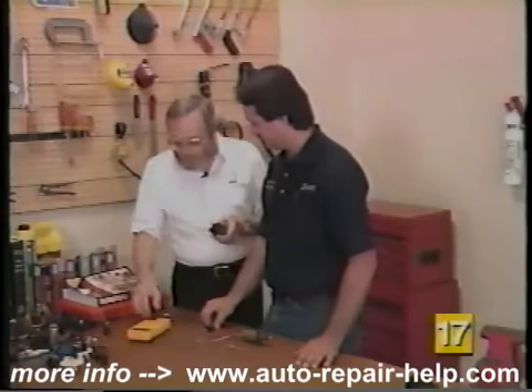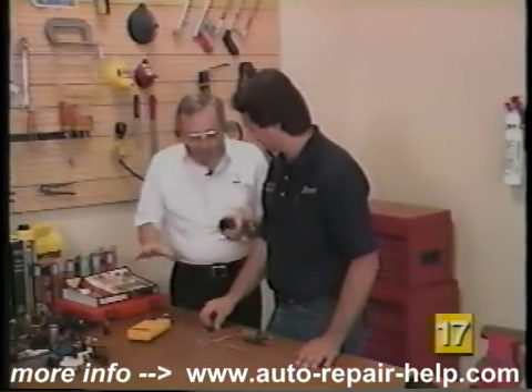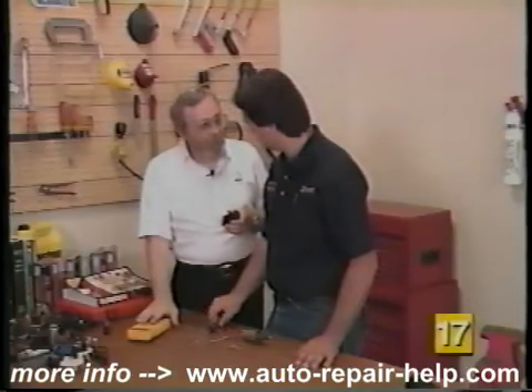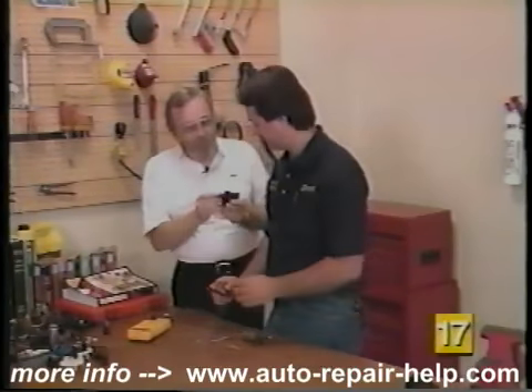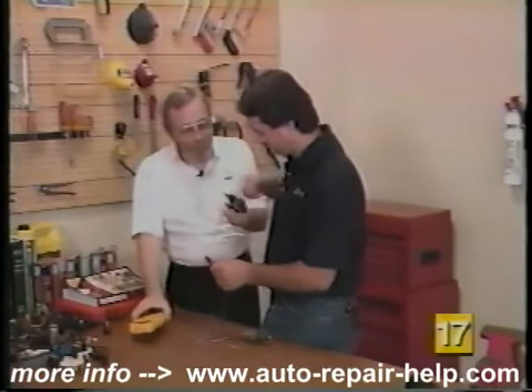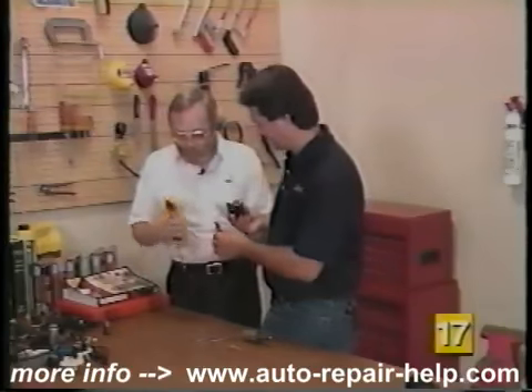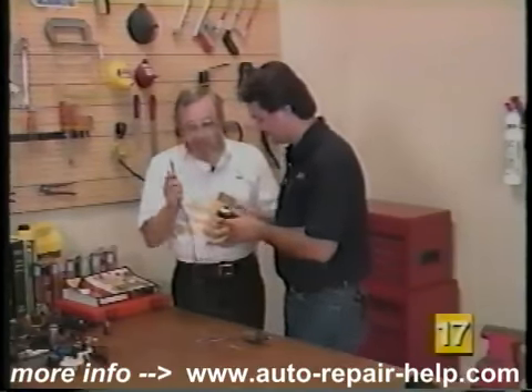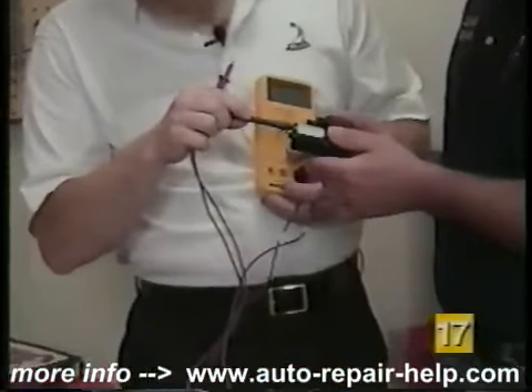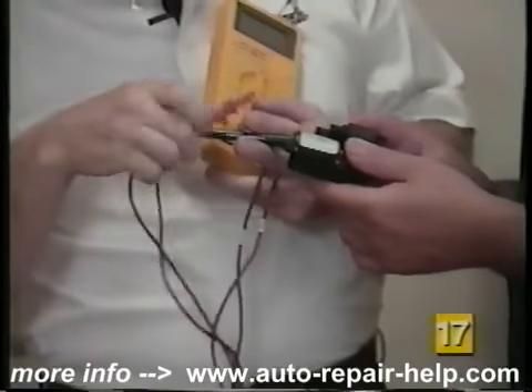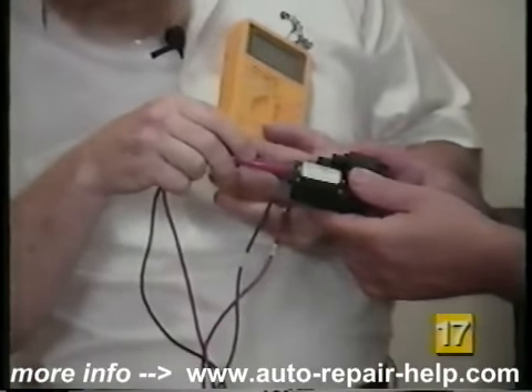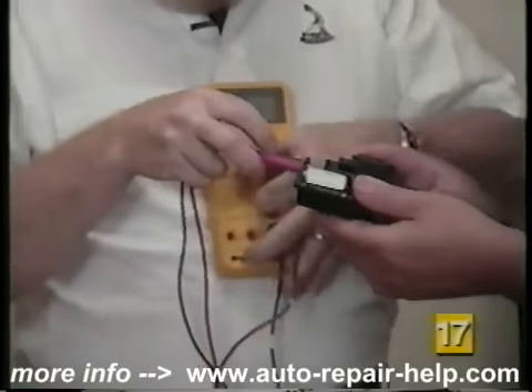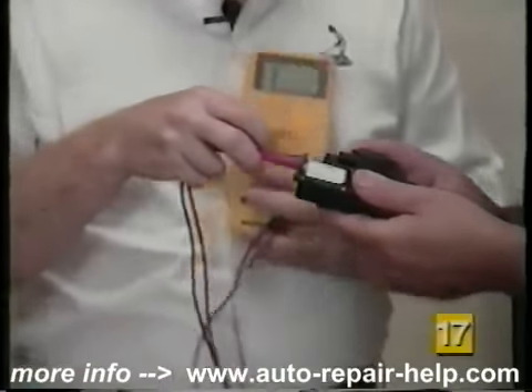So normally I like to use my meter leads as all the test equipment. Since we're still connected to the meter, why don't we just go ahead and check the nose switch. So if you'd like to hold on to that, and I'll hold the meter, and we'll put these two leads into the terminals farthest away from the motor. Remember, those are the nose switch terminals. And we'll turn the meter on.